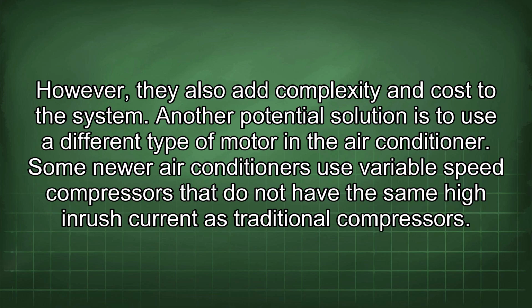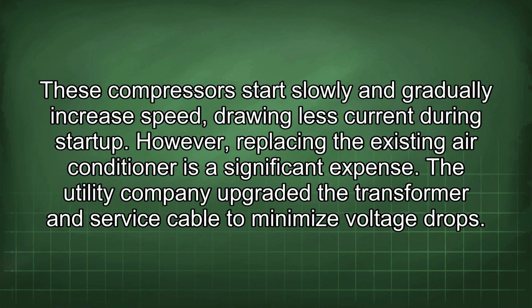Another potential solution is to use a different type of motor in the air conditioner. Some newer air conditioners use variable speed compressors that do not have the same high inrush current as traditional compressors. These compressors start slowly and gradually increase speed, drawing less current during startup. However, replacing the existing air conditioner is a significant expense.